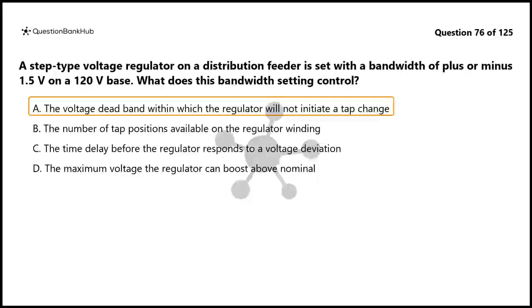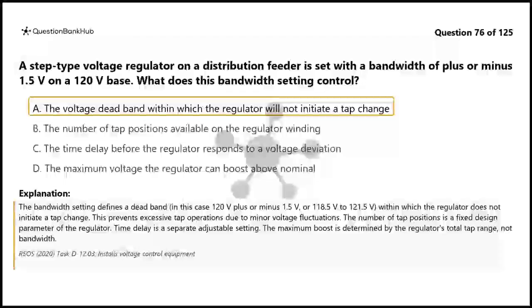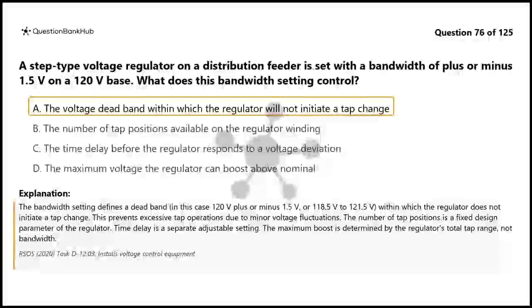The correct answer is A. The bandwidth setting defines a dead band, in this case 120 V plus or minus 1.5 V, or 118.5 V to 121.5 V, within which the regulator does not initiate a tap change. This prevents excessive tap operations due to minor voltage fluctuations. The number of tap positions is a fixed design parameter of the regulator. Time delay is a separate adjustable setting. The maximum boost is determined by the regulator's total tap range, not bandwidth.